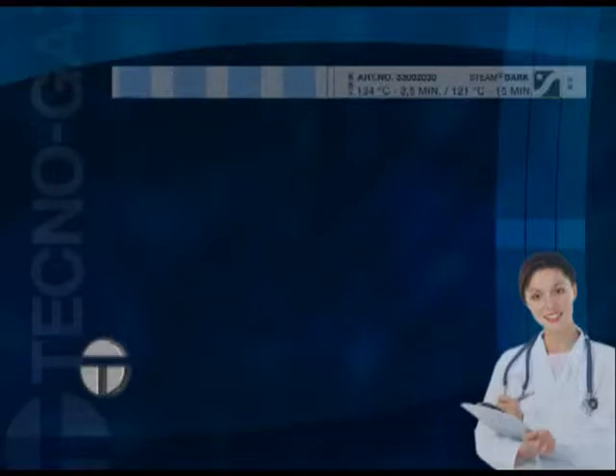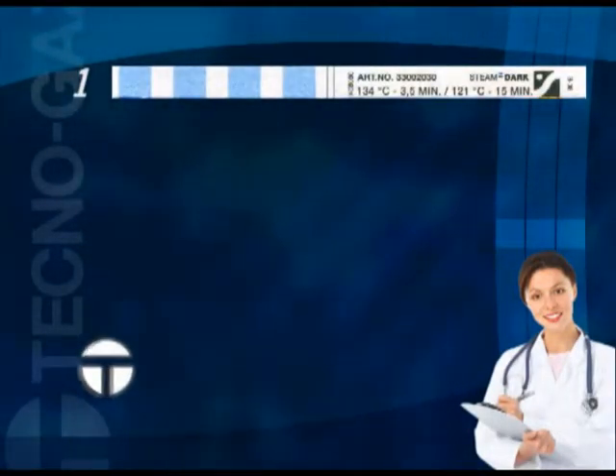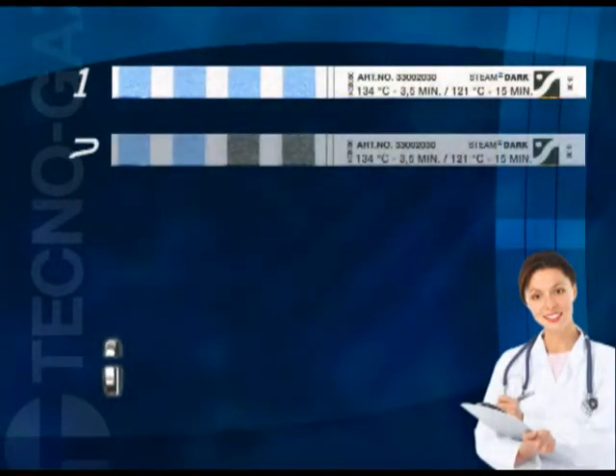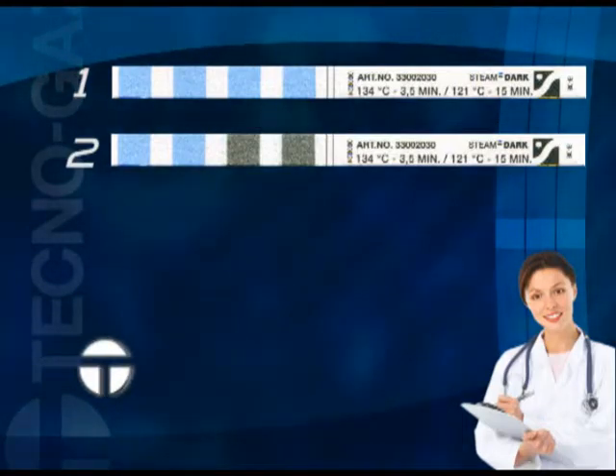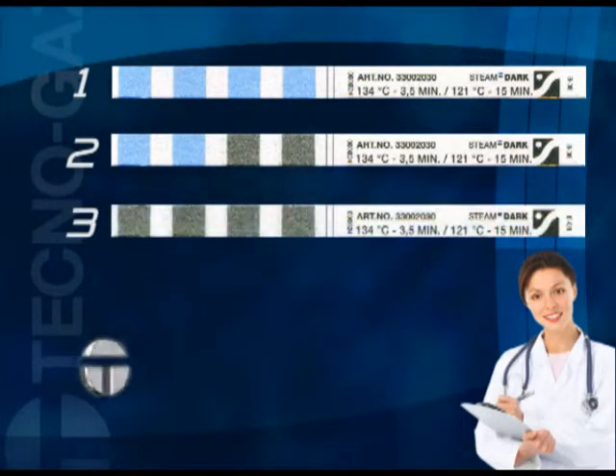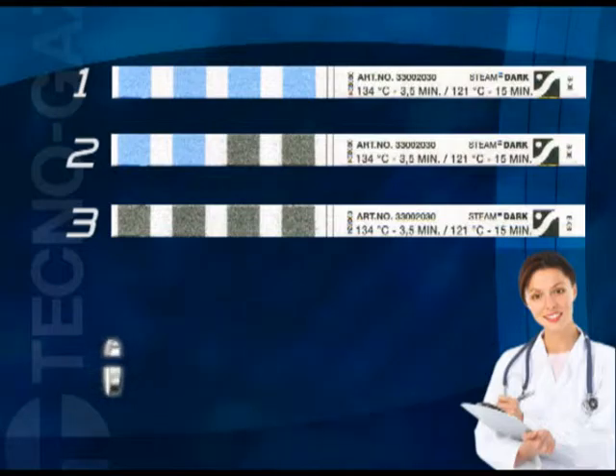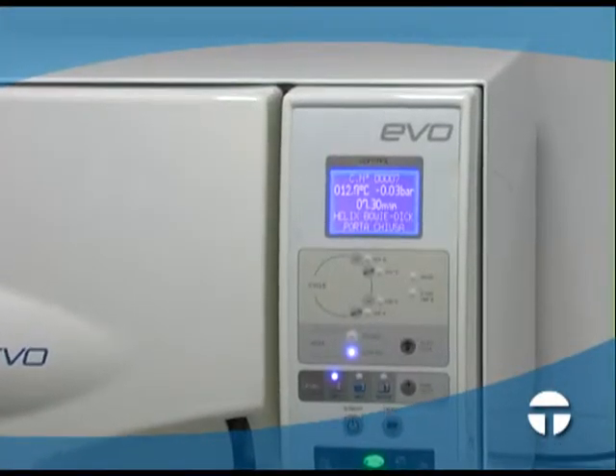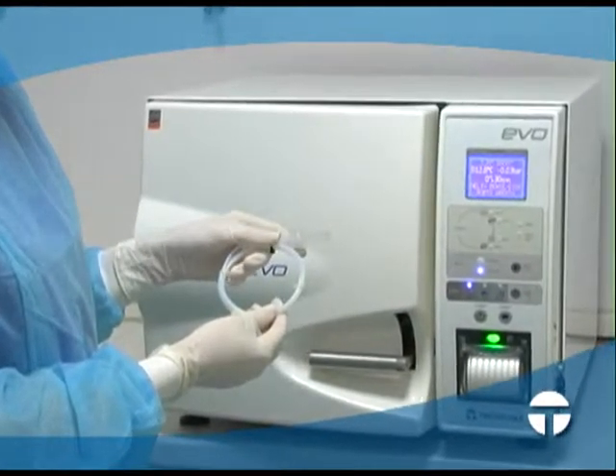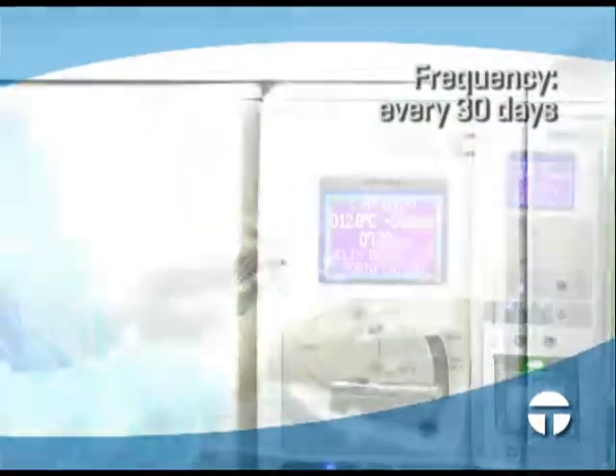Indicator 1 is in its original state. Indicator 2 shows a negative test result. Indicator 3 is positive and a perfect pass. Only those autoclaves certified for sterilizing hollow loads have to pass this test. We recommend testing every 30 days.